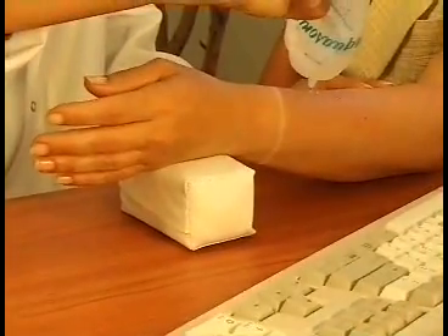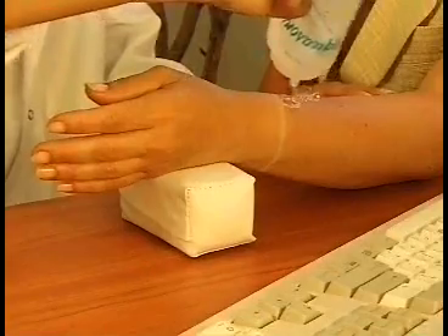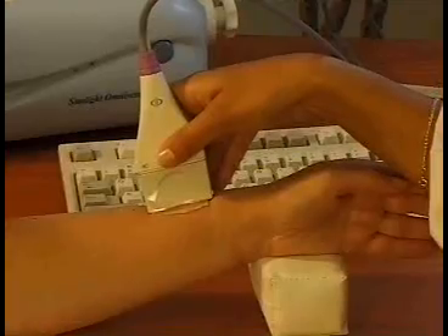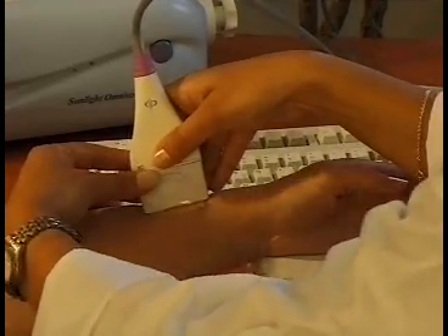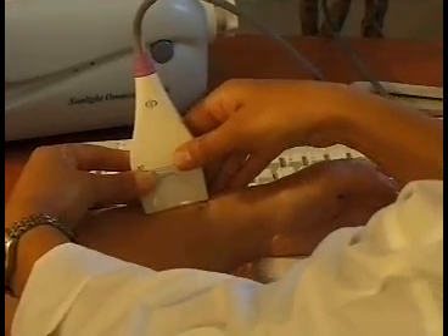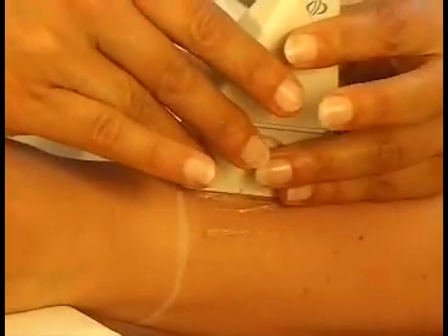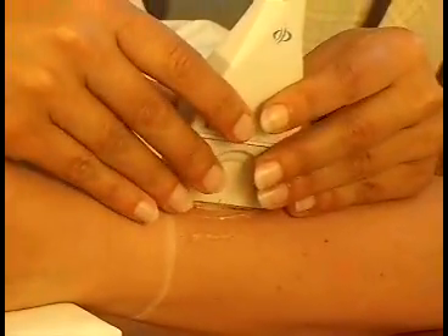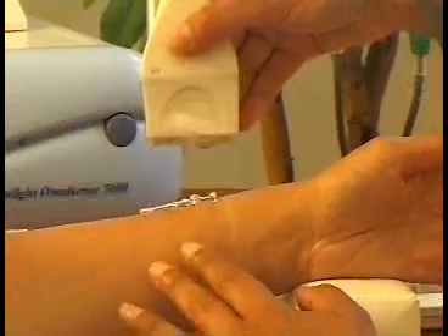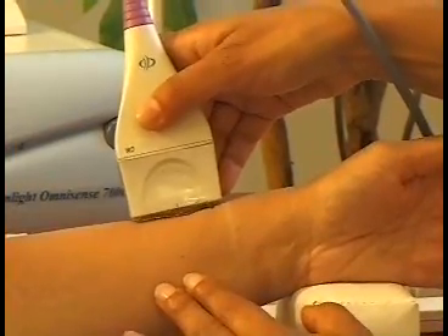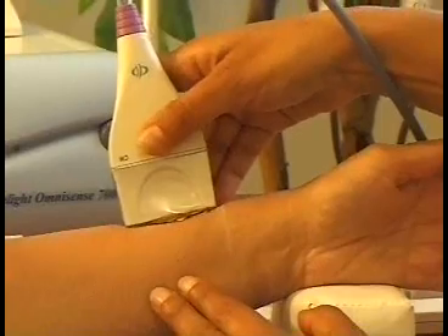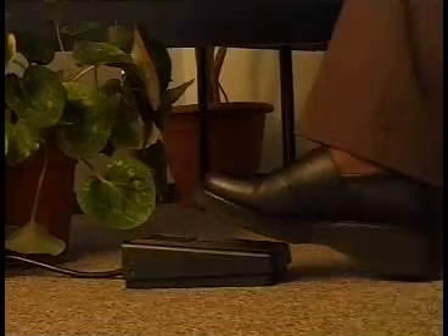Apply a uniform layer of ultrasound gel on the measurement surface. Hold the probe with both hands. Fingers 1, 2, and 3 of each hand should be holding the probe, while fingers 4 and 5 glide over the arm to keep the probe in place throughout the process. When positioning the probe, apply light pressure on the surface to be scanned.